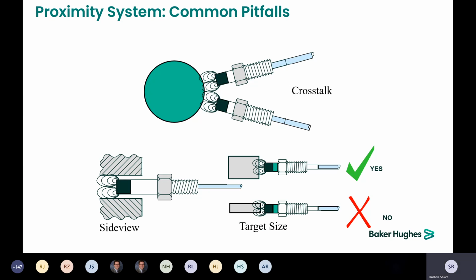Some of the common pitfalls: crosstalk. If you get two probe tips too close together, the radio fields can interfere with each other, and that causes false signals. If you're measuring a small shaft and having the two probes 90 degrees apart, or if you have a Keyphasor in the same area, you may need to shift one probe axially along the rotor to just prevent the two from interfering with each other. Generally, you want to have at least 2 to 2.5 times the probe tip diameter between the center lines of the probes. So if you're talking about an 8mm proximeter, you want at least 20 millimeters between center lines.